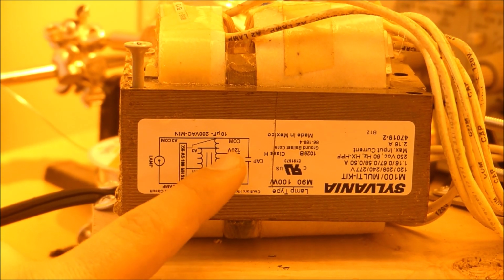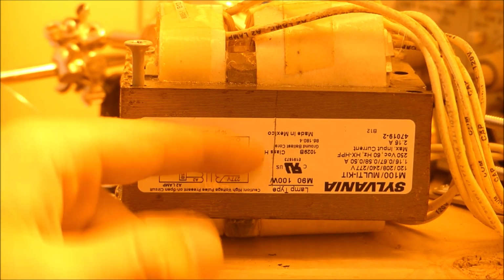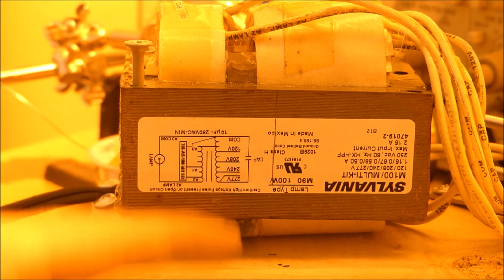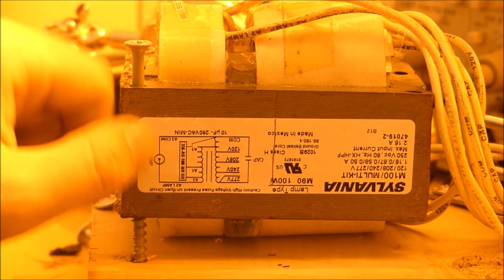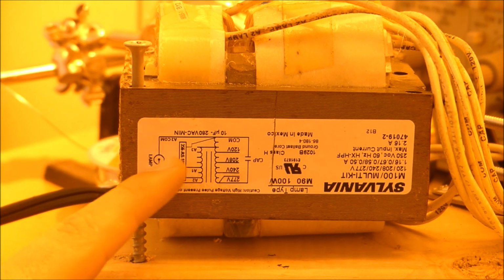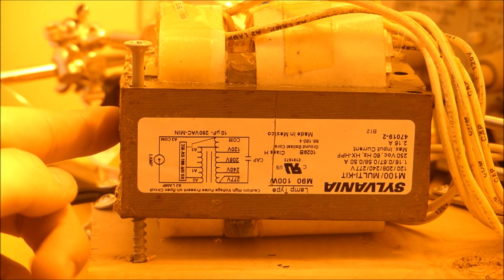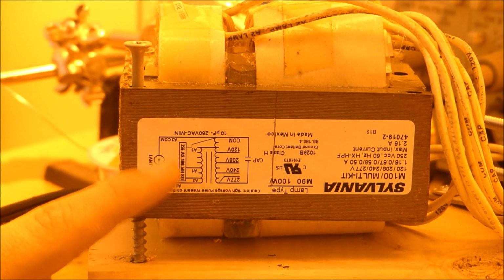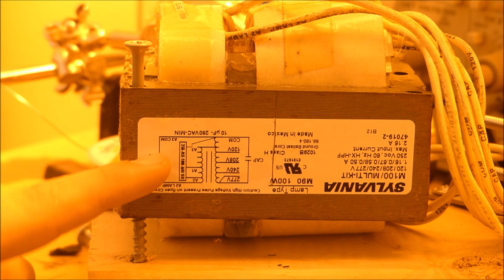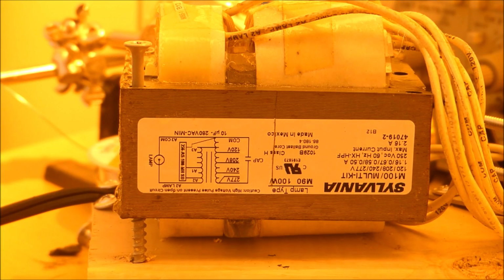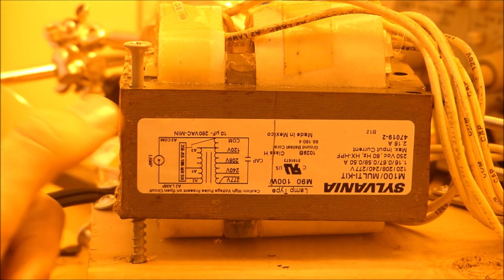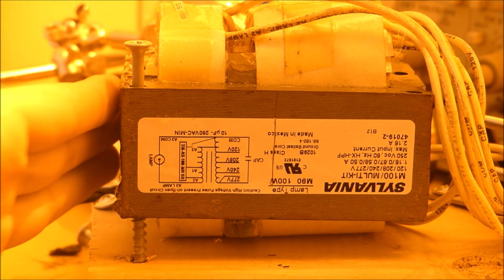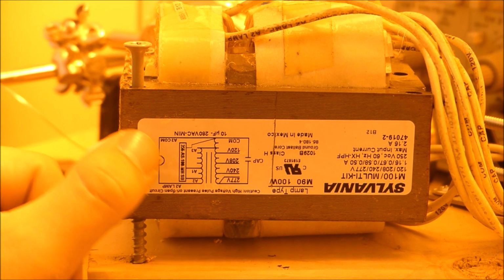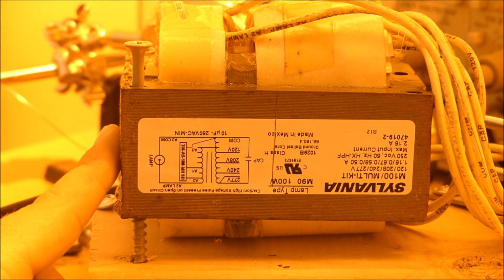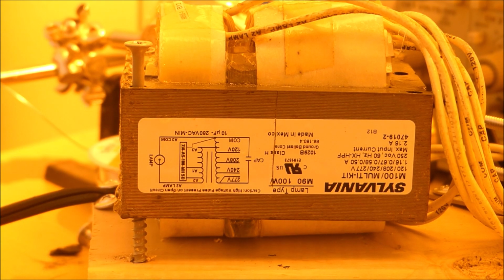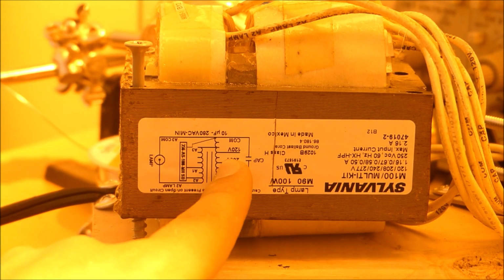Alright, now the reason this capacitor here is acting as something called a power factor correction capacitor, is because in setups such as this high intensity discharge lighting that uses a magnetic ballast transformer, some current flowing into this transformer is being used to power the light bulb, but some current is just being used to generate the electromagnetic flux in the transformer. That means that not all the current being drawn by this circuit is being used for a useful purpose without this capacitor in place.